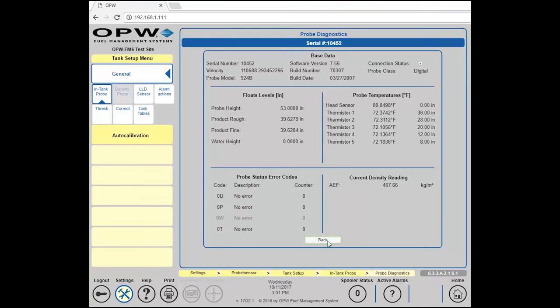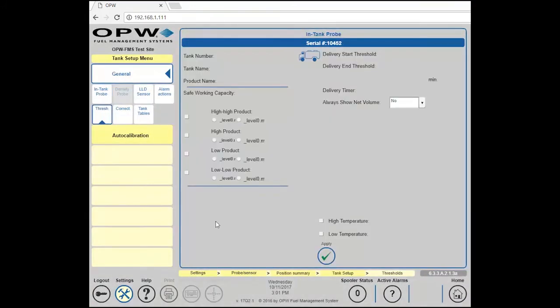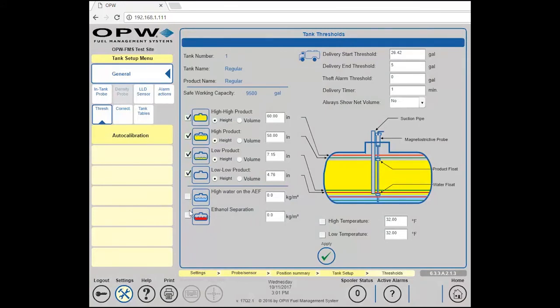Once we have that number, and it will normally run somewhere in the vicinity of 725, 727, something like that, then we want to add about 50 to that, and that gets us what our ethanol separation level should be. So we have to click the boxes to make those alarms active. Then in ethanol separation, if we were at 725 halfway through the product in the tank, we would set this at about 775. And then for our high water on the AEF, go about 25 or so more than that, so we would just set it at 800. Now, if you try to go too low or too high here, the system will note that and will not allow that input to be applied. So we have our numbers. We click apply. All of our thresholds are updated.